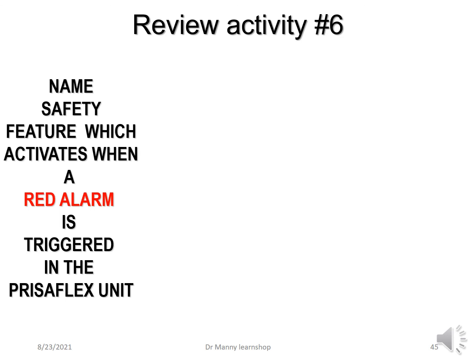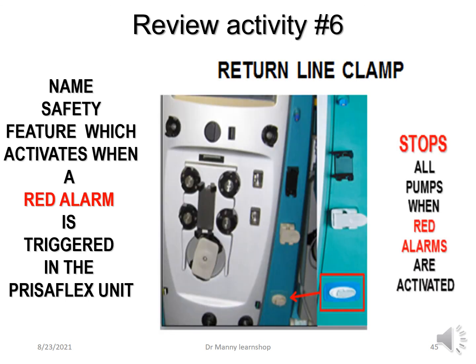Okay, this is the last review activity. Name the safety feature which activates when a red alarm is triggered in the Prismaflex unit. The safety feature which is triggered is the return line clamp. And this activates when you've got a warning or a malfunction alarm, a red alarm. And it stops all the pumps when the red alarms are activated to prevent anything bad happening to the patient.